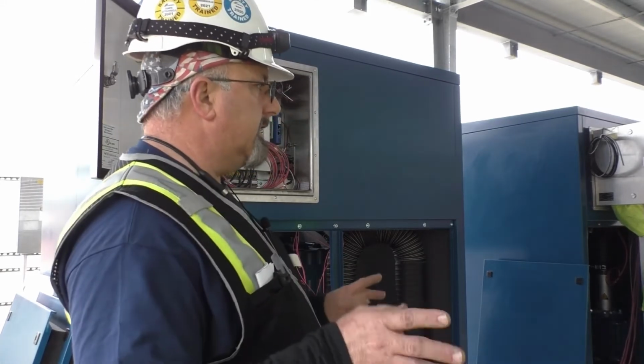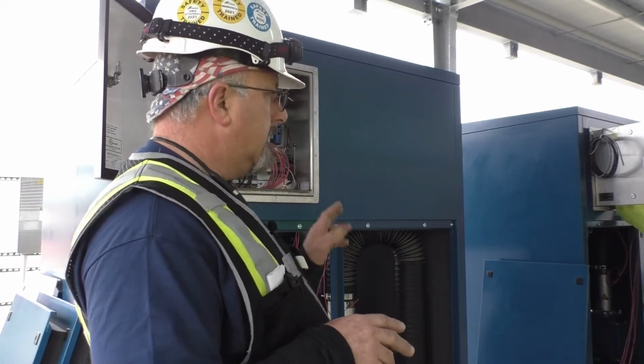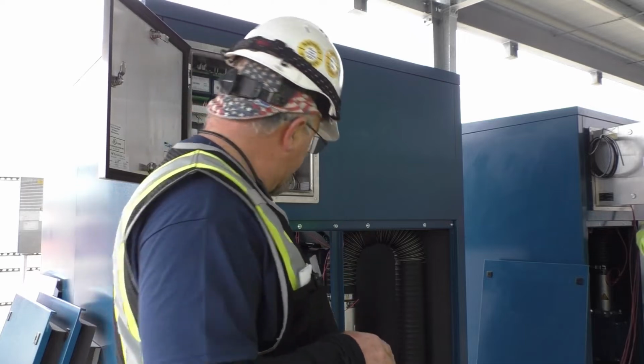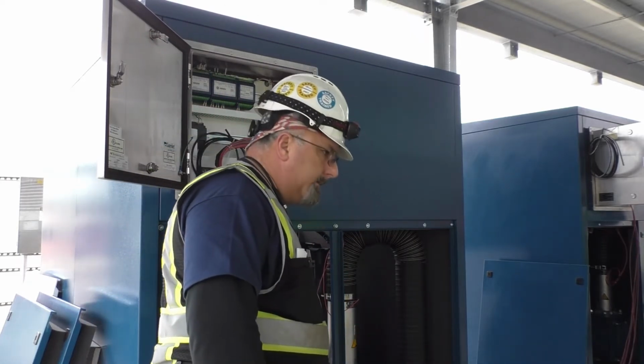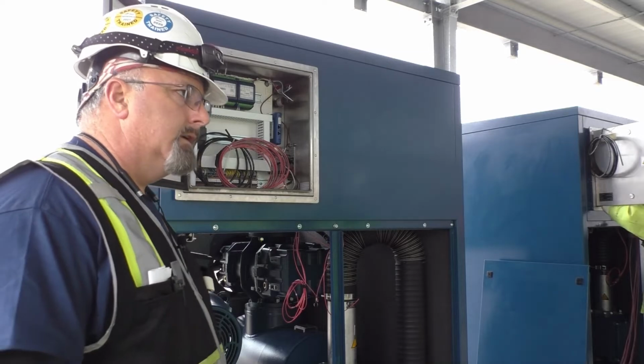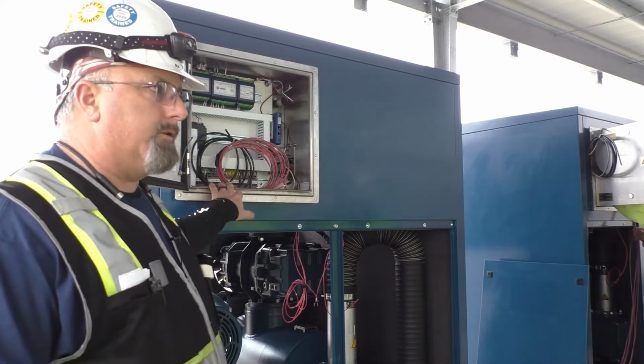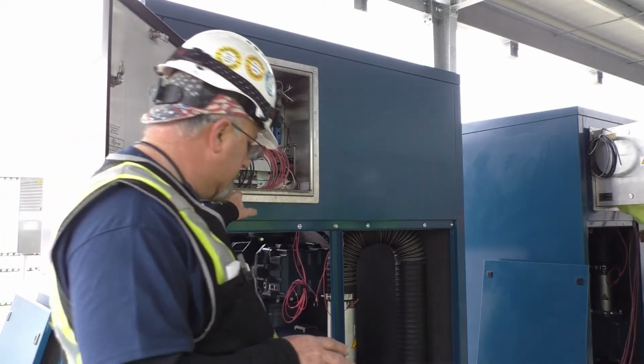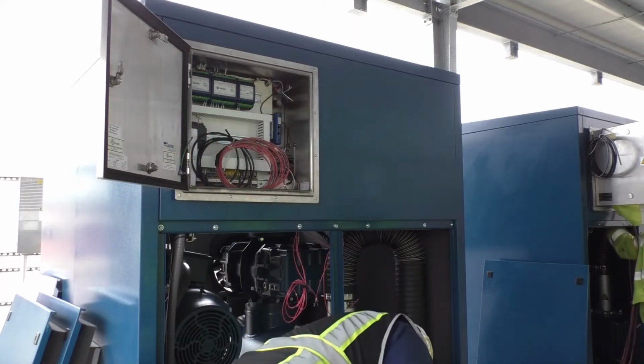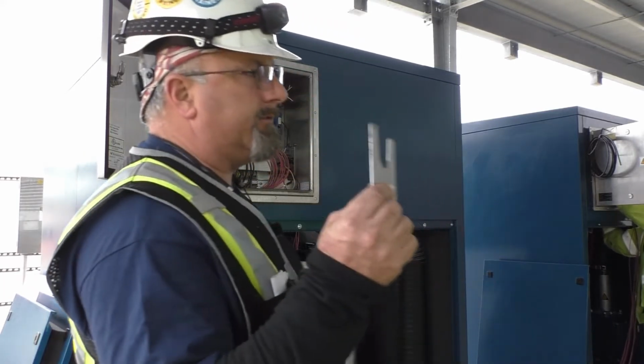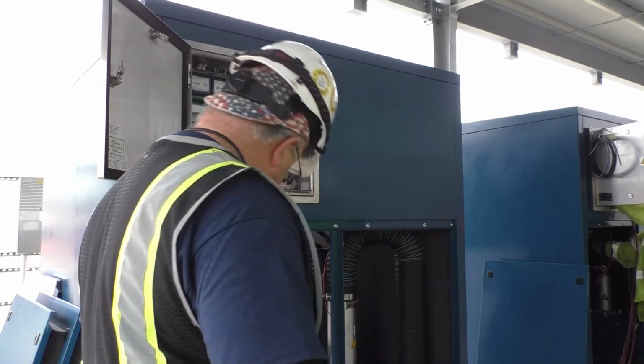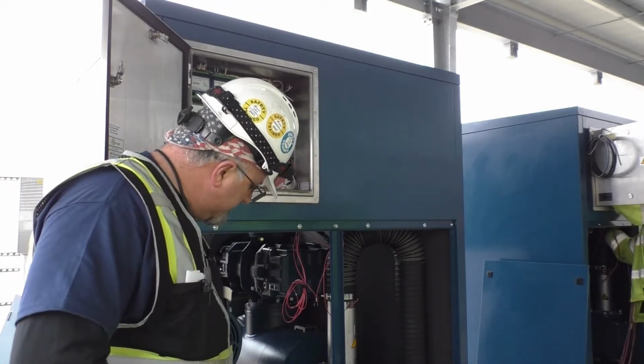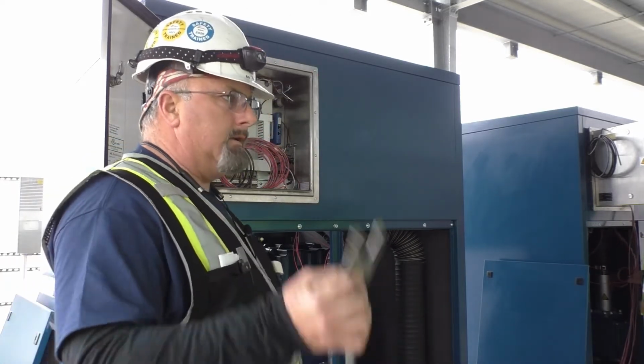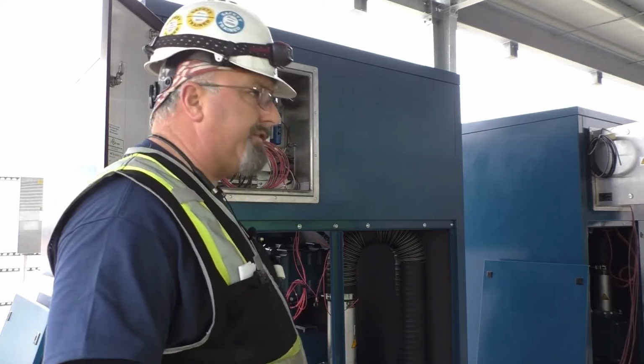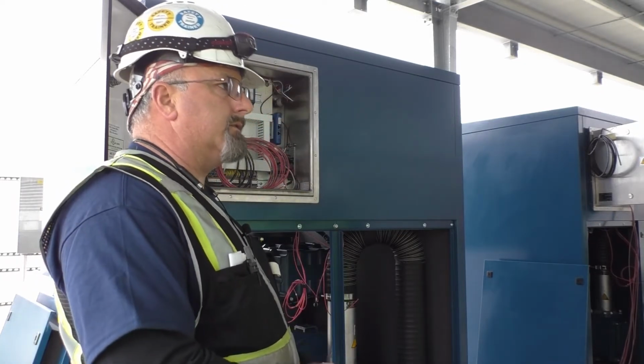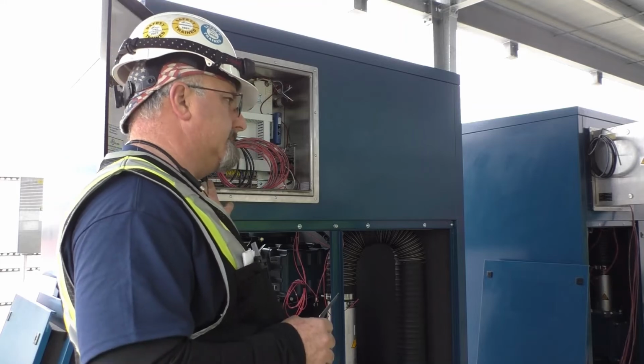Now, if you have to level the blowers, the small ones have 3 of these vibration isolation mounts in them. These blowers have 4. So if you were to have to level the blower, there will be some extra shims left over from where I leveled them. If you look down on this side and the front, you can see where I put those in between the base frame and those resilient mounts. That is how you level these blowers.